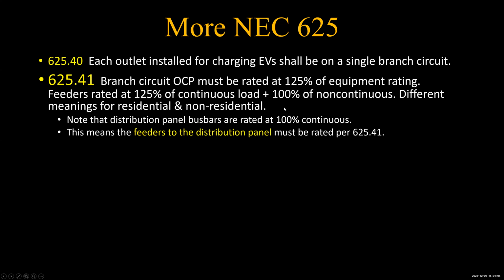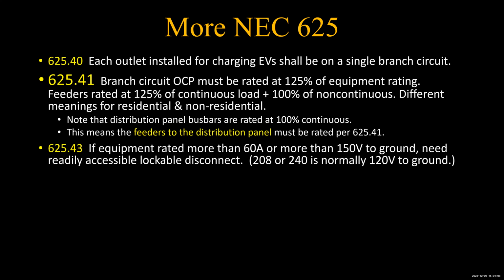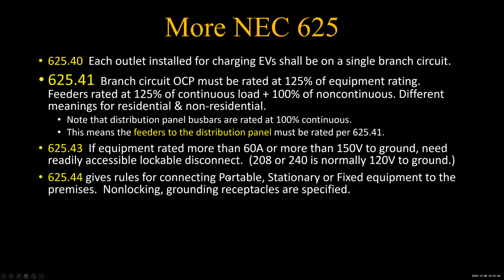Okay, so 625.43. If the equipment itself is rated at more than 60 amps and more than 150 volts to ground. Now that "more than 150 to ground" is an interesting statement, because keep in mind with the 120/240 or even a 120/208, the highest voltage to ground for either leg is 120. The 240 volts is from line to line, but each line individually is 120 volts to ground. So it has to be more than 150 for this to apply. But if that's the case, then you need a lockable disconnect. And so it may come up, not very common.